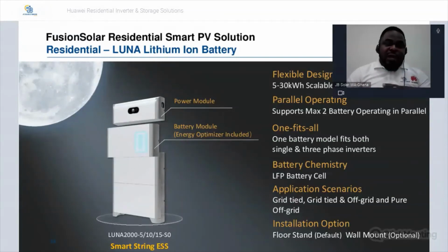The battery is modular — it's a lithium-ion battery that comes in modules: battery modules and a power module. Each battery module is 5 kilowatt hours, and you can have a maximum of 3 battery modules in a rack — so 5, 10, 15 kilowatt hours, which is the maximum with one power module. You can have one power module with one battery module at 5 kilowatt hours, or one power module with 2 battery modules for 10 kilowatt hours.